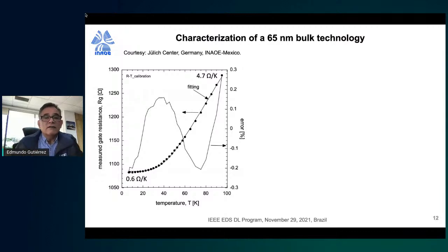This is the calibration plot. We measure the gate resistance as a function of temperature in the black dots, and then we extract the error. The error is pretty low, in the range of 0.3%. And that is the calibration curve that we use for using the polygate as a thermometer.